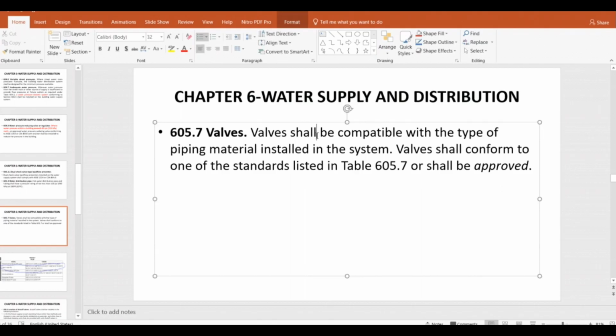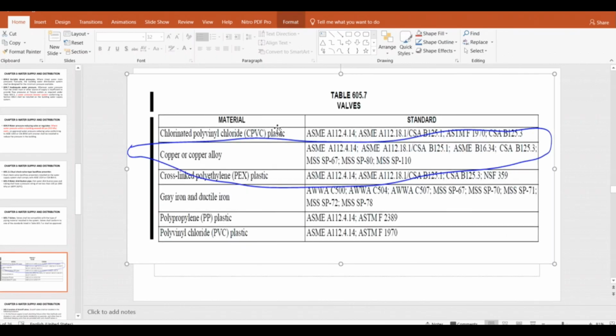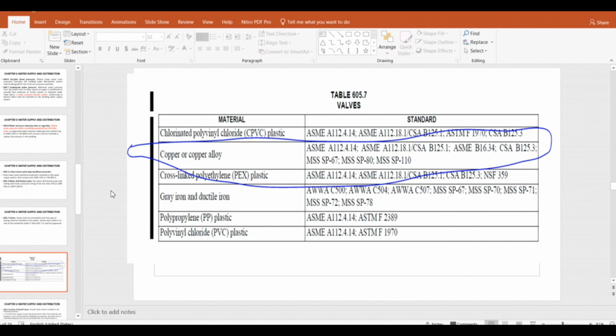Okay, so valves shall be compatible with the type of piping material, because now we have different types of valves. We are fixing the valve with the pipeline, so both should be compatible for the connection. Here we have one example from the IPC. You can see all the standards are about AWWA, based on the American standard. But countries like Qatar and UAE normally follow the British standard, so the valve standard will vary compared with the IPC. There is no rule that only the American standard from this table will be selected for the whole plumbing system. We can use the British standard also, based on the local requirement, to select the valves.